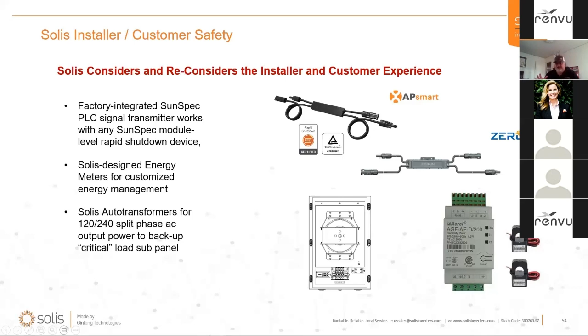It includes 2 CTs that you're going to put on the L1, L2 of your service panel where you're making your point of connection. And this device is going to communicate with the inverter with the same kind of wiring that you saw on that BYD wire. So you're actually going to have 2 communication devices coming into the hybrid, one from the battery and one from this power meter that comes with the inverter. And once you get those 2 wired up, you're essentially ready to commission the inverter. And like Devin says, it's kind of the heart of the system. You'll be able to commission the inverter in different ways. Let's go to the next slide.